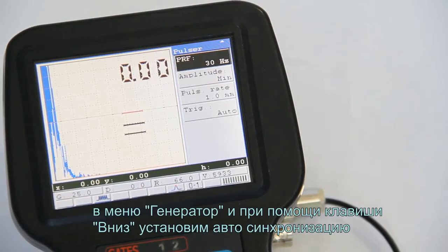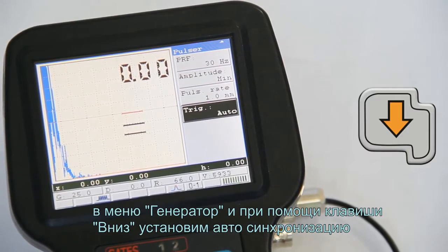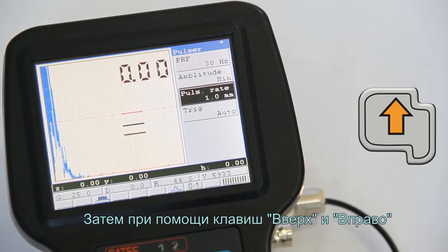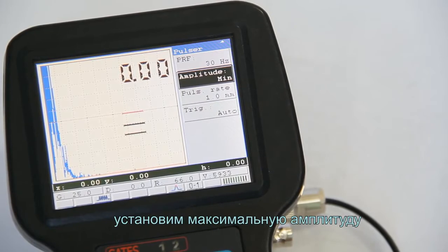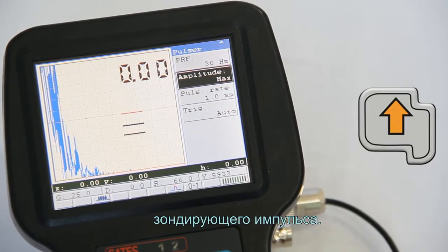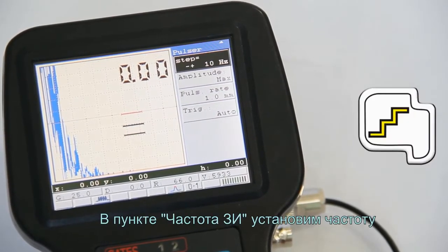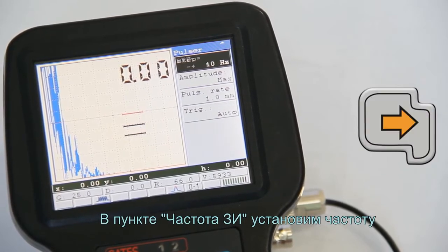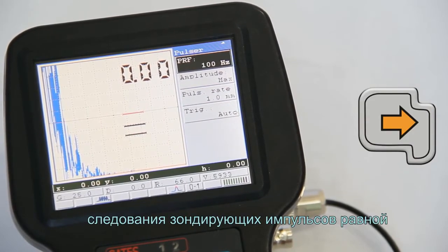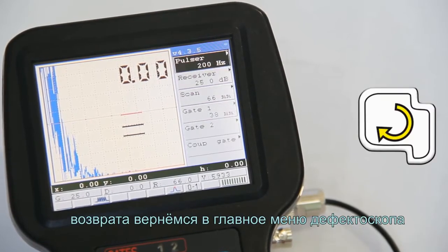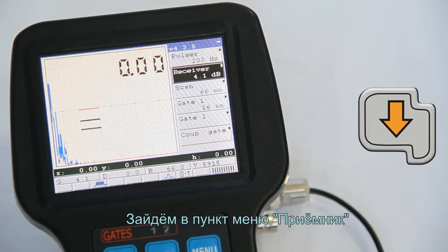Then by pressing the Enter key, enter the pulser menu and using the Down key, set the auto synchronization. Then using up and right arrow keys, set the maximum amplitude of the initial pulse. In the PRF item, set the initial pulse frequency that equals 200 Hz. Then using the Return key, return to the main mode of the flaw detector.